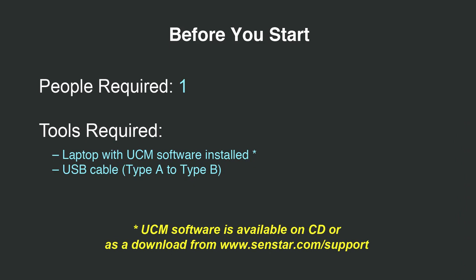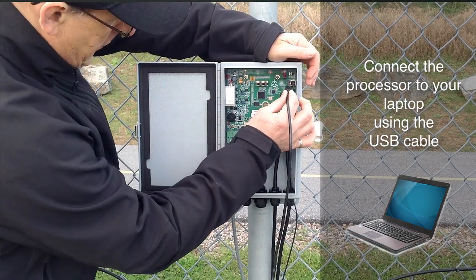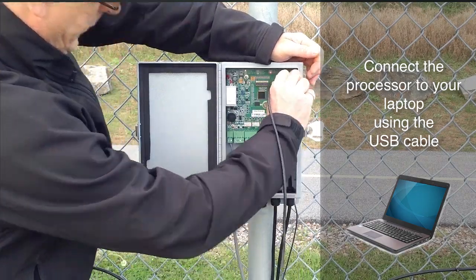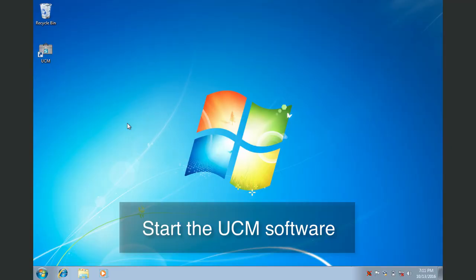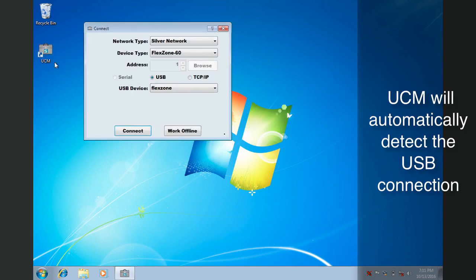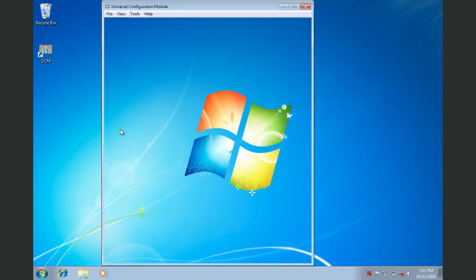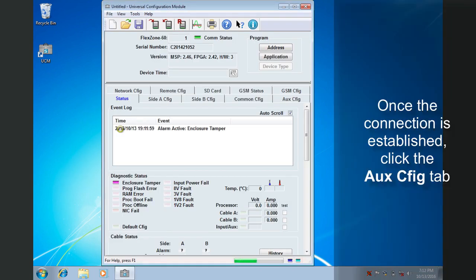To configure the relays, you will require a Windows laptop with the SenStar UCM software already installed and a USB cable. Connect your laptop to the FlexZone processor with a standard USB cable. Start the UCM software. The UCM software will automatically detect the FlexZone processor. Click Connect.